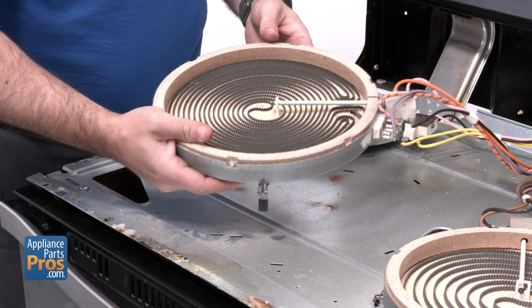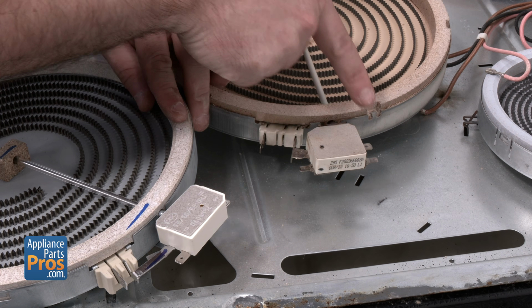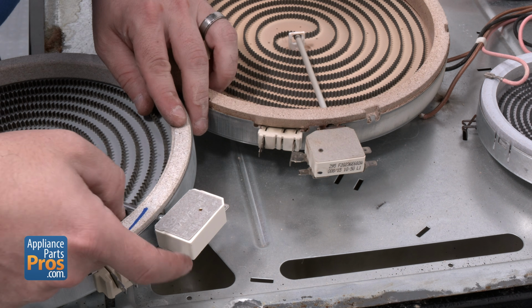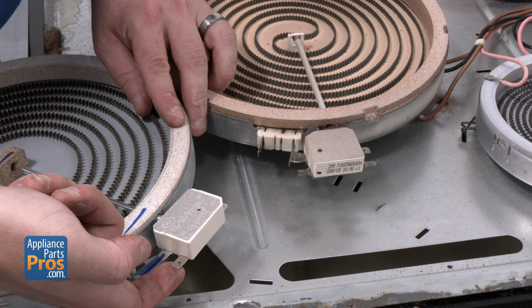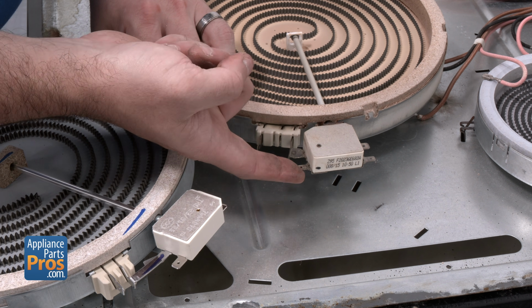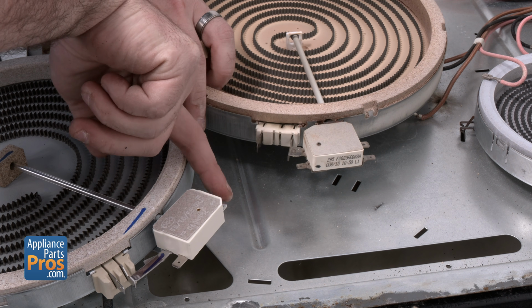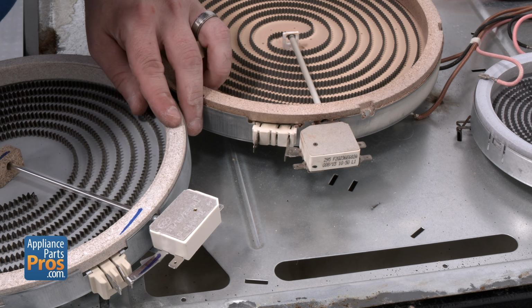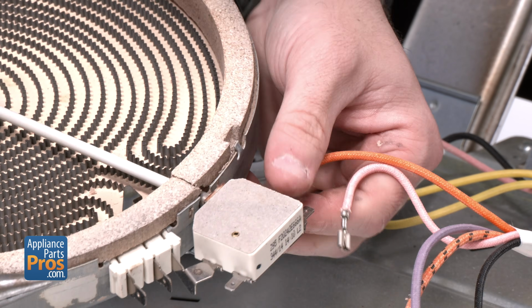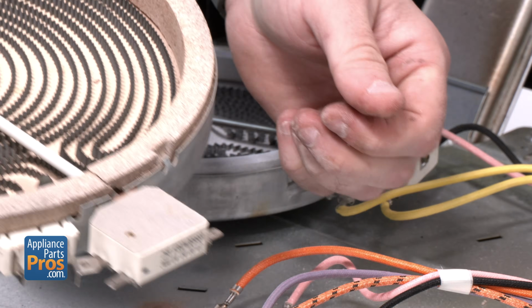Turn the element around so you can see the terminal markings. Note the label for each wire position before disconnecting anything. For example, the orange wire attached to terminal 2A on this element will connect to the terminal labeled 2A on the new element. Follow this process for each wire so the new element is wired exactly the same. Once the wire positions are confirmed, disconnect the wires from the old element.